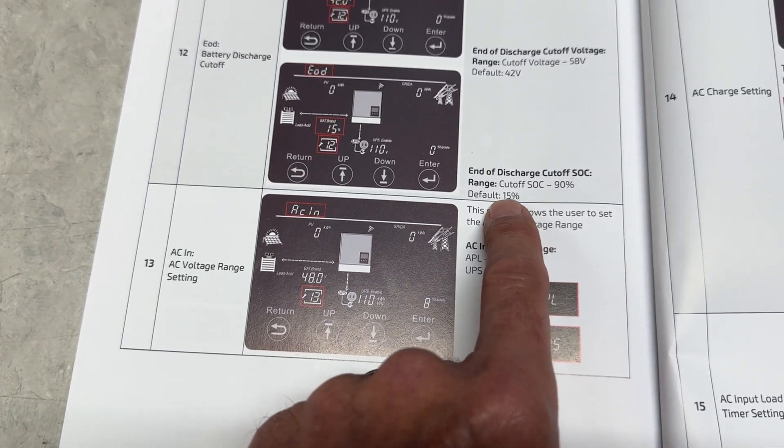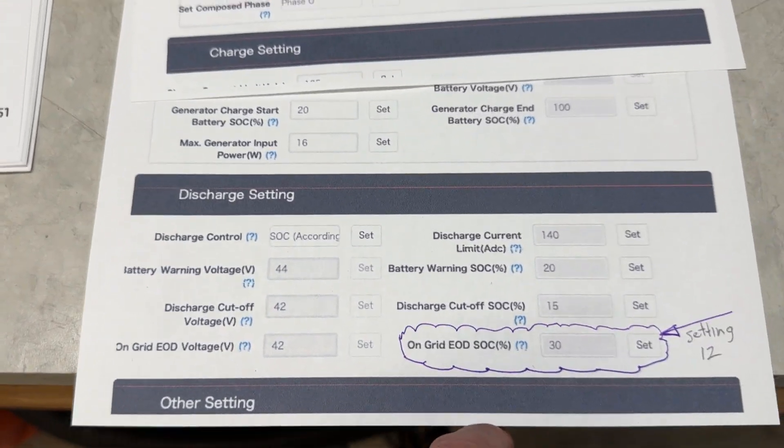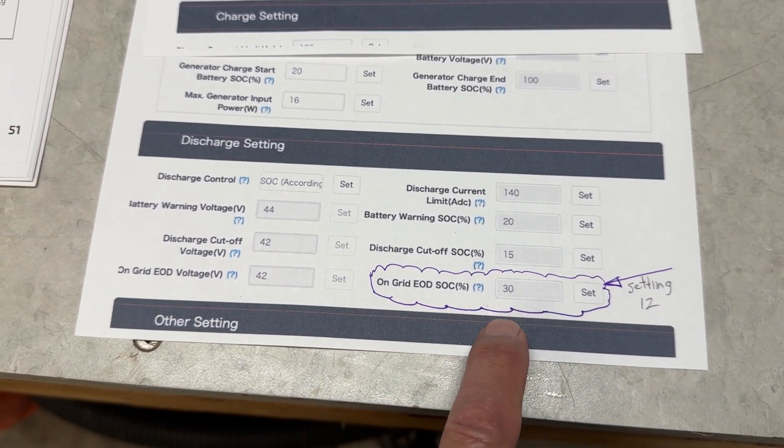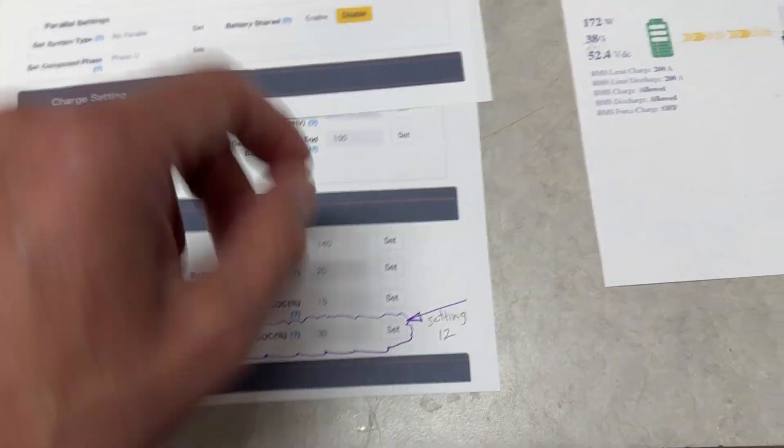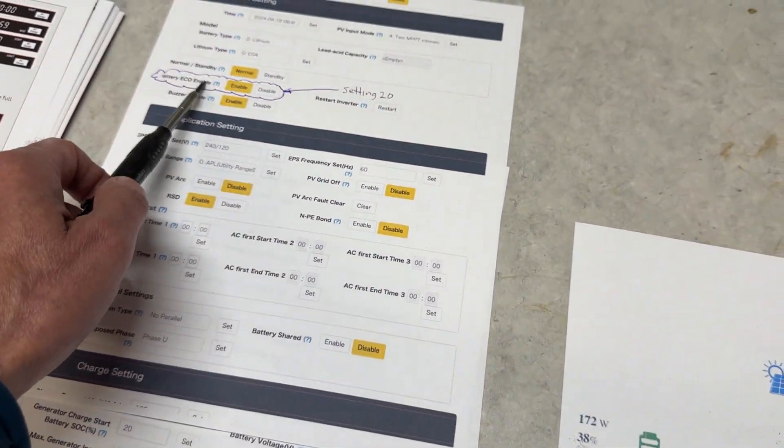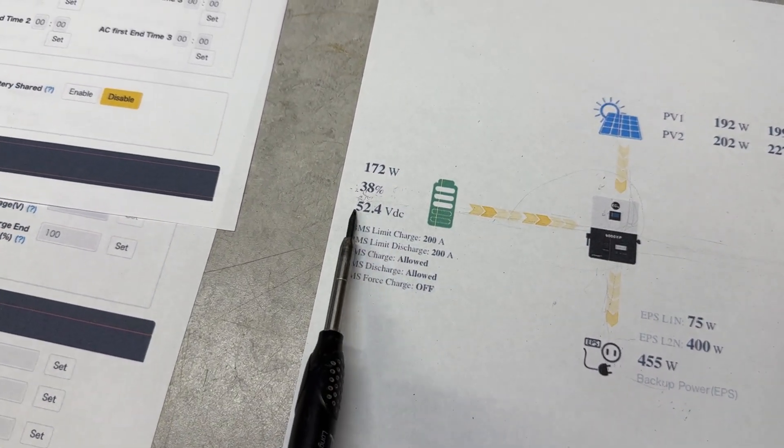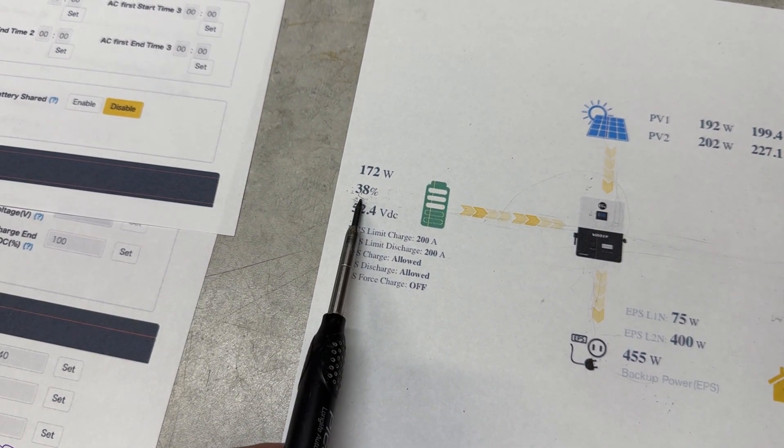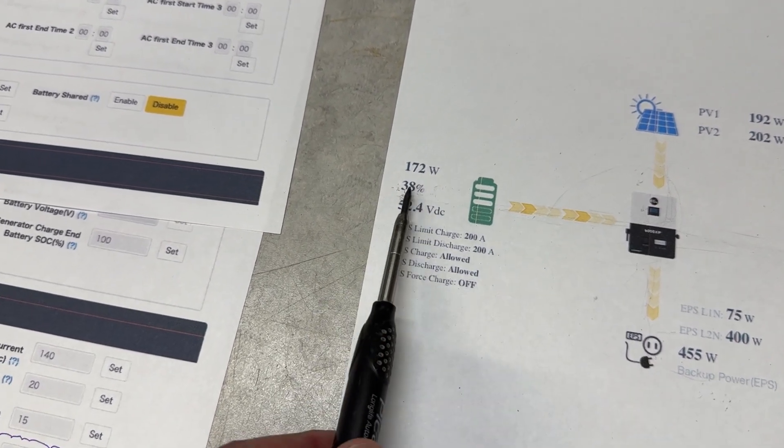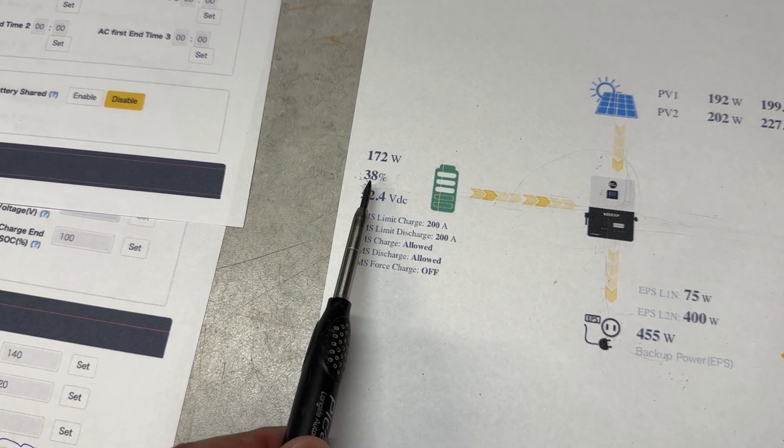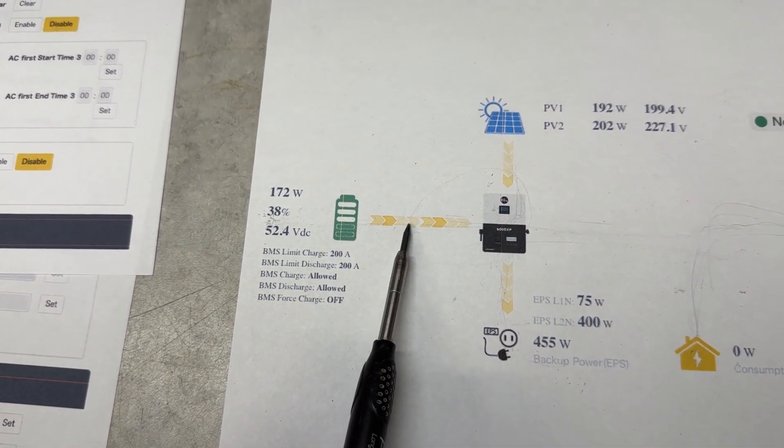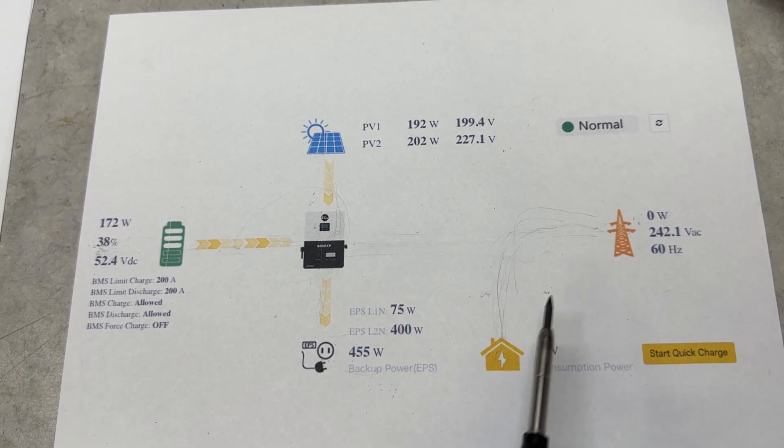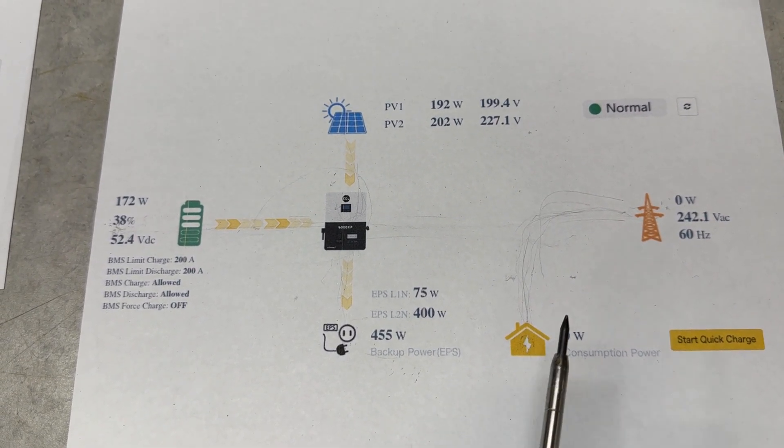By default it's set to 15 percent and I have it set to 30 because I wanted a little more buffer than 15 percent. So what does that do? When the battery here gets to 30 percent—actually it's your setting minus one percent—so if I have it set to 30 percent, when it reaches 29 percent it will disconnect the battery and do the bypass mode, so then the grid kicks in and supplies power to the house.